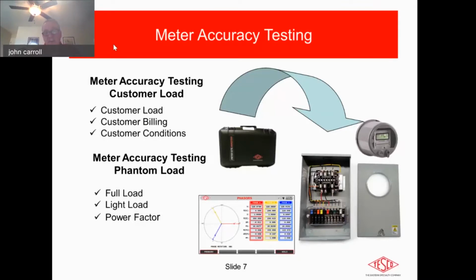One of the key components here, as we've mentioned, is the CTs and PTs that are providing the ratio and the current to the meter. The problem is, if there's something wrong at that point, the meter, despite the fact that it could be a smart meter, may not necessarily know that. So it's still very accurate, but it's accurately wrong because the current is not where it should be. So there are 2 general ways that we approach this in an in-service situation.